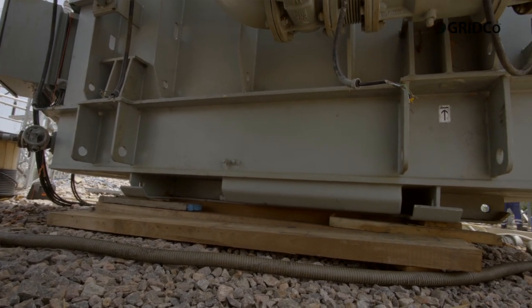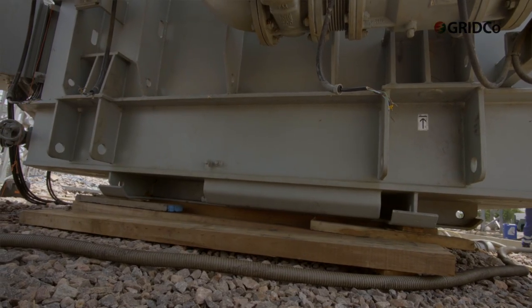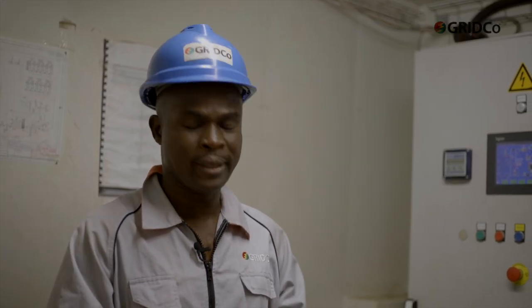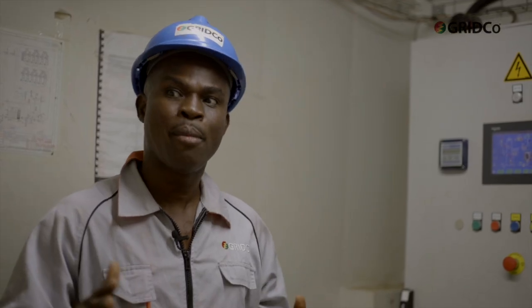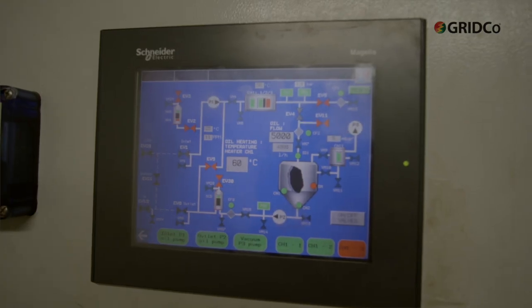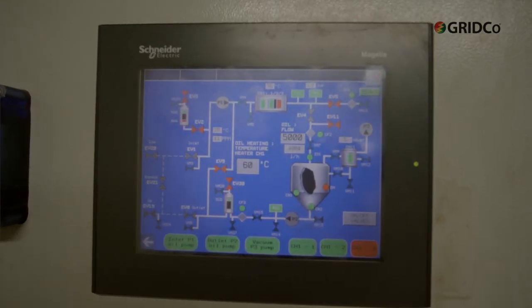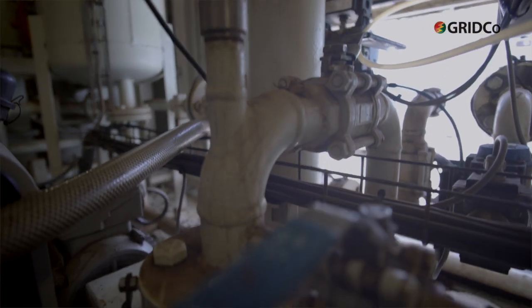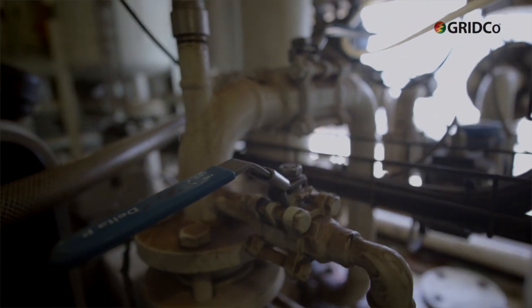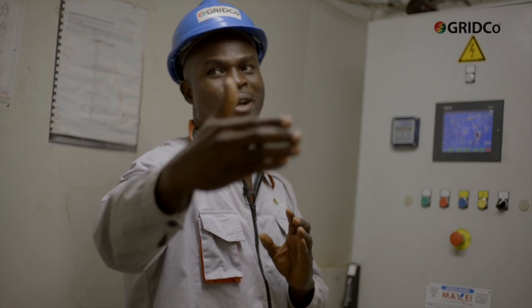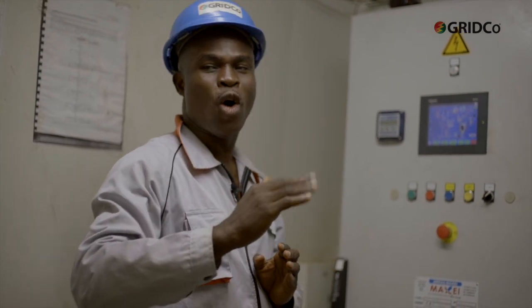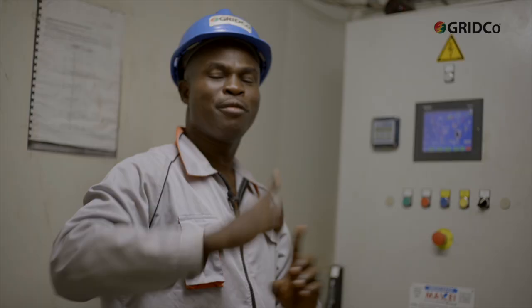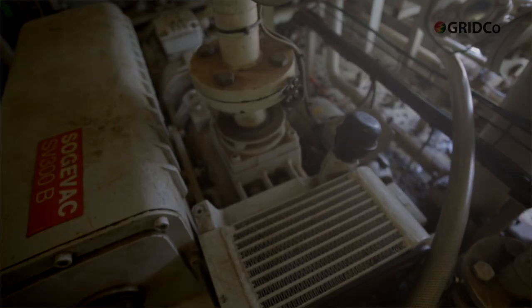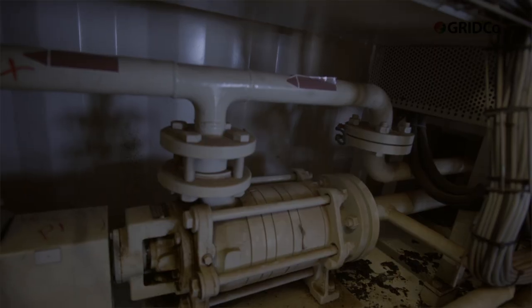bringing the transformer from a far distance together with the oil. There's a need for us to make sure that the oil is within acceptable level as far as our moisture is concerned. Basically what we are doing is taking the transformer oil from the transformer, heating it up to a certain temperature level. Water basically boils at 100 degrees, while the transformer oil, when we heat it almost up to 60 to 70, is equivalent to our water boiling at 100 degrees. And therefore, as a result of that, the moisture in the oil is completely vaporized.